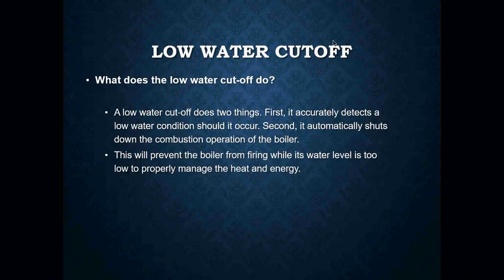Your low water cutoff does two things: first, it accurately detects a low water condition should it occur; second, it automatically shuts down the combustion operation of the boiler. This will prevent the boiler from firing while its water level is too low to properly manage the heat and energy that the burner is introducing into that boiler.